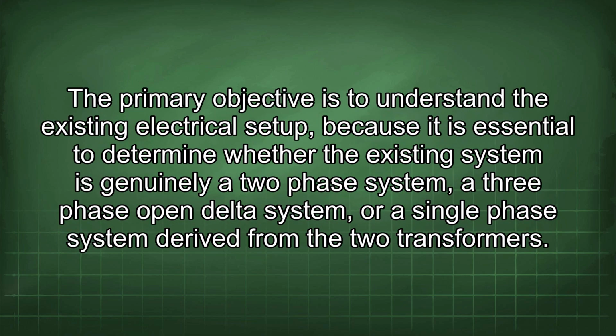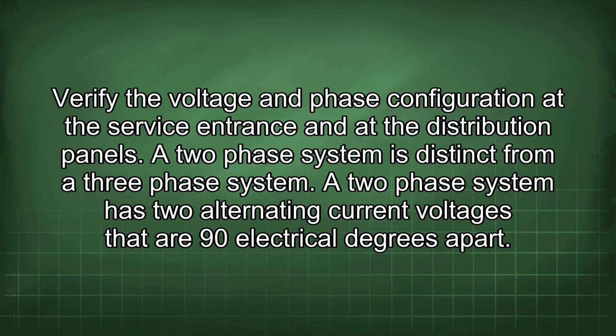The primary objective is to understand the existing electrical setup, because it is essential to determine whether the existing system is genuinely a 2-phase system, a 3-phase open delta system, or a single-phase system derived from the 2 transformers. Verify the voltage and phase configuration at the service entrance and at the distribution panels.